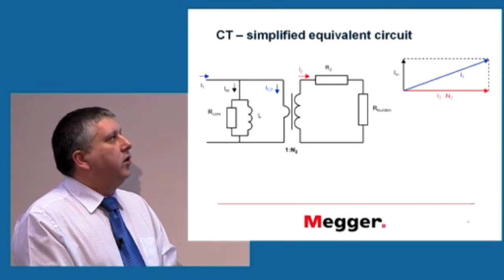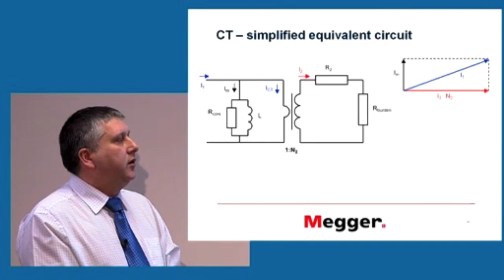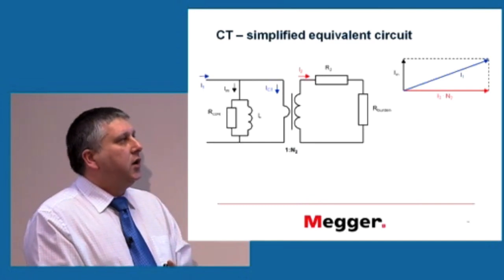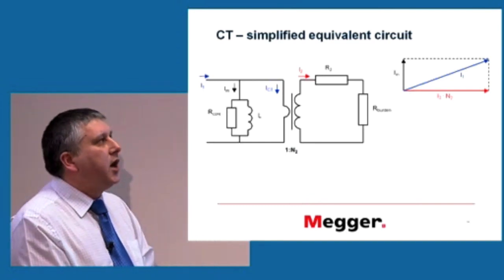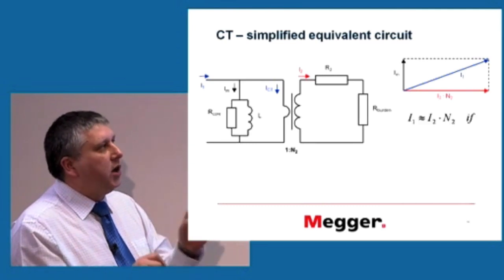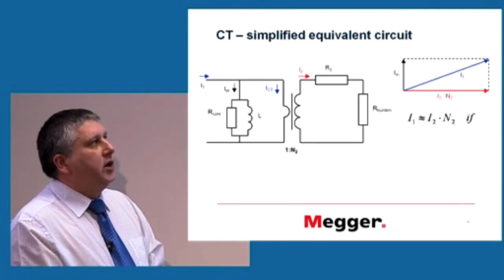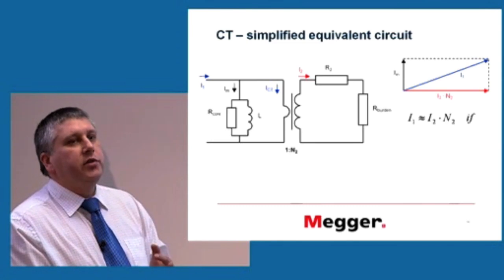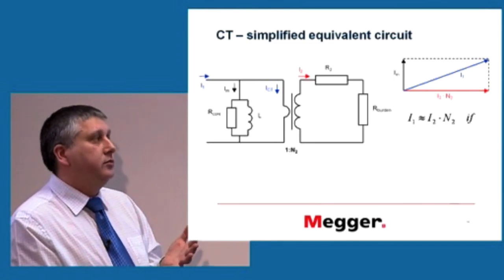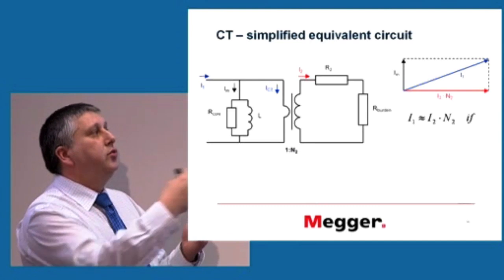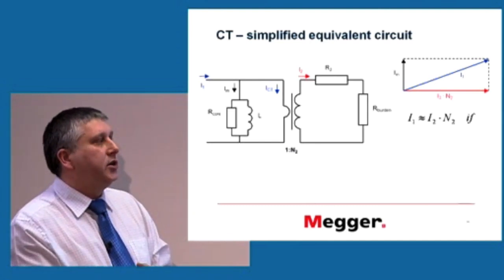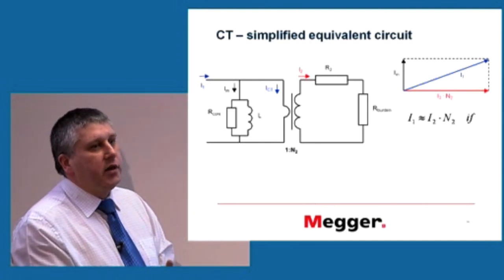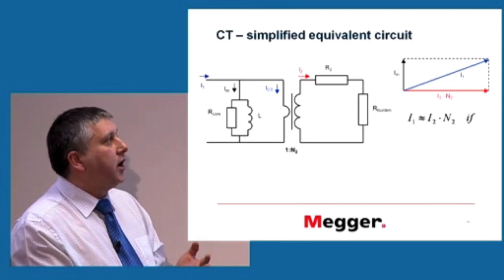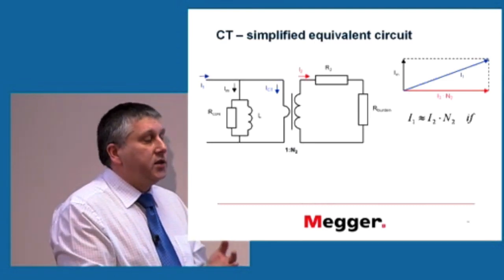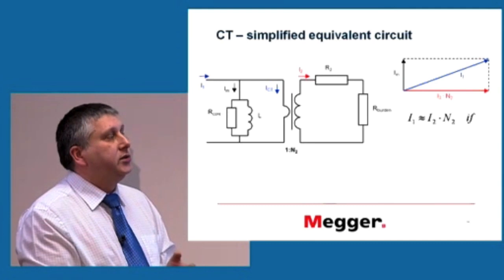If we look at the currents and the vectors of what happens, we roughly get that the total current supplied to the current transformer will be a combination of what we see at the secondary side, divided by the number of turns - so it has to be multiplied to be transferred to the primary side - and the magnetization current, which sort of takes into account the inductance of the primary and the losses.